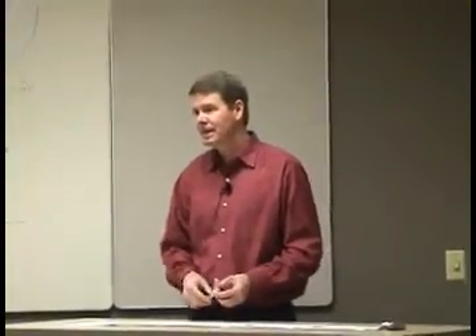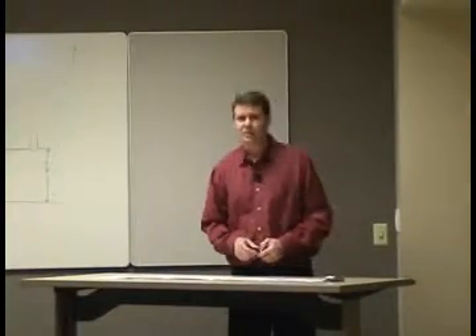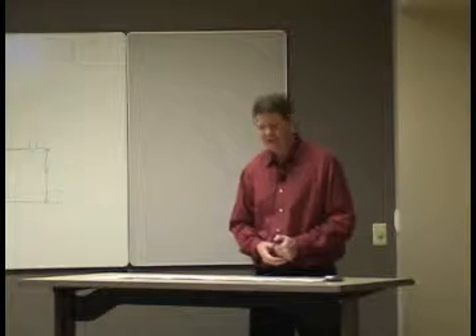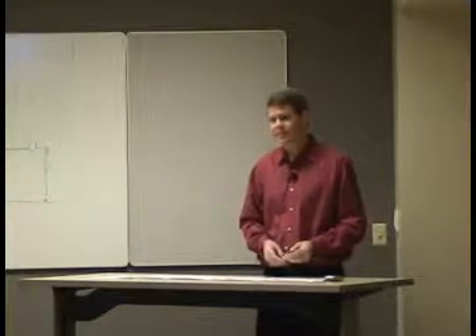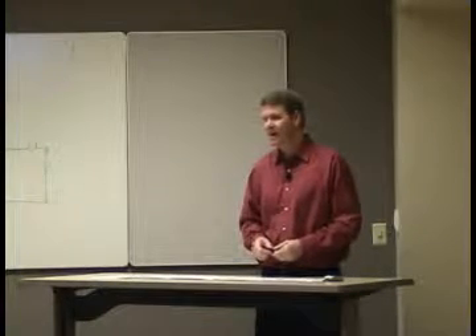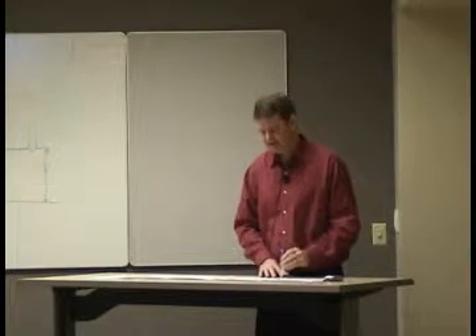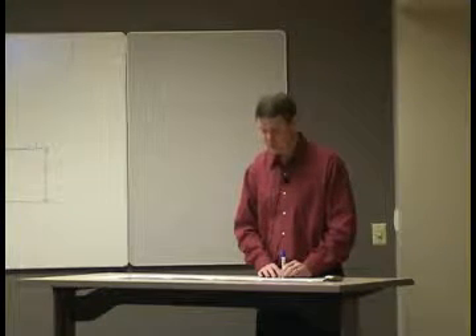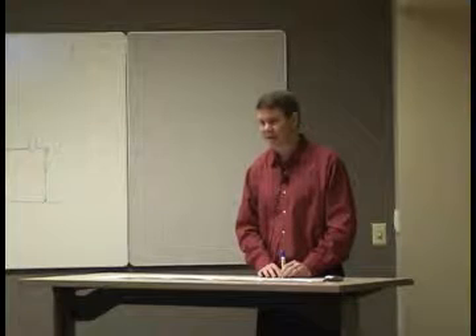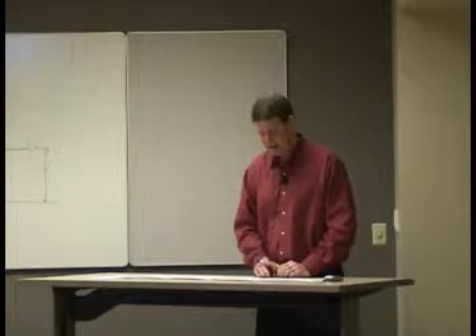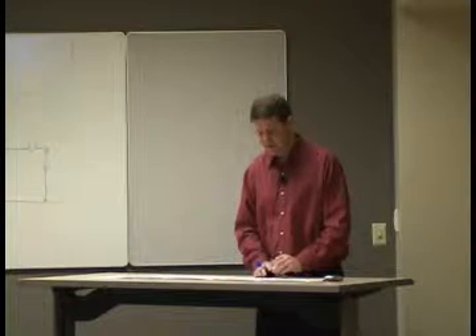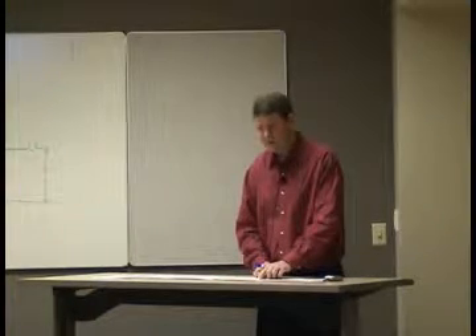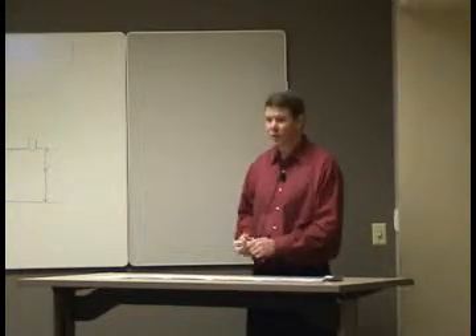Okay, since this is a VAV system, the engineer's telling me I want the minimum CFM to be 300 CFM. Because if you pump 900 CFM into that room all the time, it's going to freeze them out. So we're going to have to back it off to 300 as our minimum. So at 300 CFM, what's our velocity pressure? Let's solve backwards and go through the math there, and I come up with 0.0465 inches of water column.